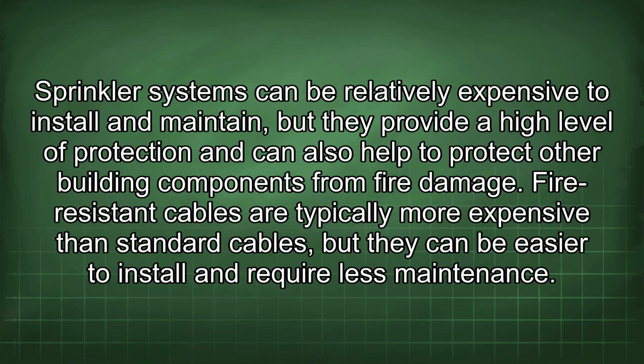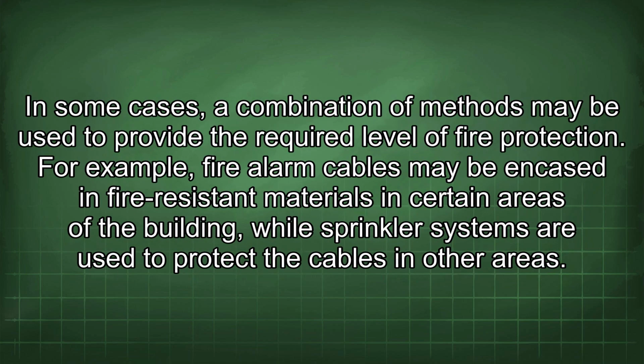Sprinkler systems can be relatively expensive to install and maintain, but they provide a high level of protection and can also help to protect the building components from fire damage. Fire-resistant cables are typically more expensive than standard cables, but they can be easier to install and require less maintenance. In some cases, a combination of methods may be used to provide the required level of fire protection. For example, fire alarm cables may be encased in fire-resistant materials in certain areas of the building, while sprinkler systems are used to protect the cables in other areas.